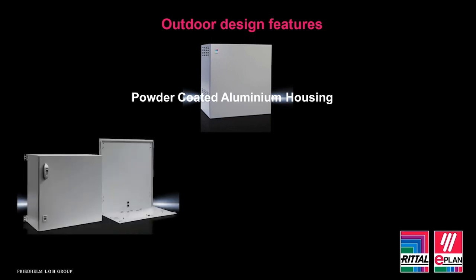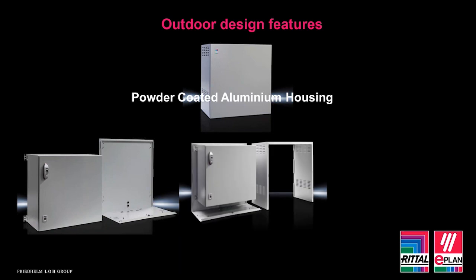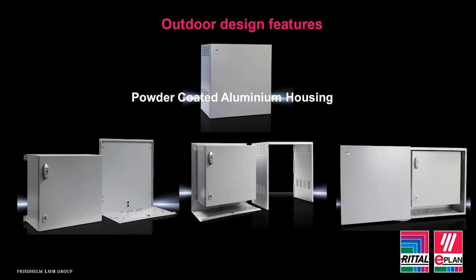So we can see here that an internal enclosure, it's a standard sheet steel enclosure. However, the outer housing is a powder coated aluminium and simply fits around the existing enclosure. This means that the seals are now protected and the enclosure is directly protected from the elements. Whilst it's not necessarily the best solution, there's substantially more protection than was there before.